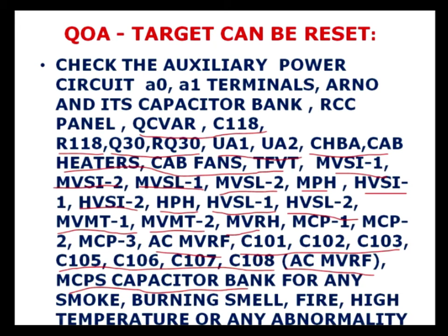MVRF and their contactors C101, C102, C103, C105, C106, C107, C108 pertaining to AC MVRF. MCP capacitor bank also has to be checked for any smoke, smell, fire or high temperature or any other abnormality. In case there is any abnormality, extinguish the fire with the fire extinguisher, isolate the defective auxiliary and resume traction with proper precautions. If everything is normal, reset the relay target and resume traction.